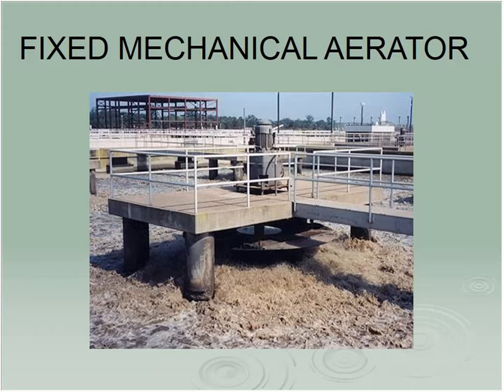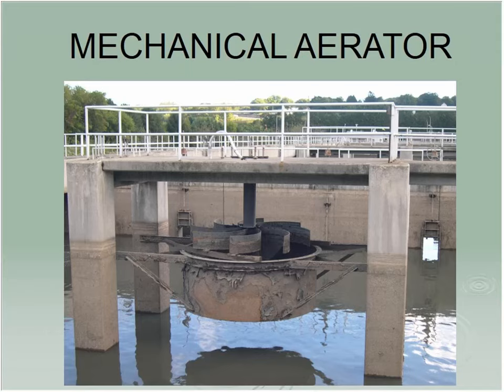The other thing, if you walk out here, there's always vapor in the air with these things. So now I'm ingesting that stuff. Plus, you walk out onto that bridge in the middle of February without your cleats on, it's pretty darn slippery out there. Not a great thing. That's what those aerators look like. They sit inside that well, literally feeding the air into that water. And you control it by the speed of the mixer itself, or you can raise and lower the water level with the submergence of the blade.